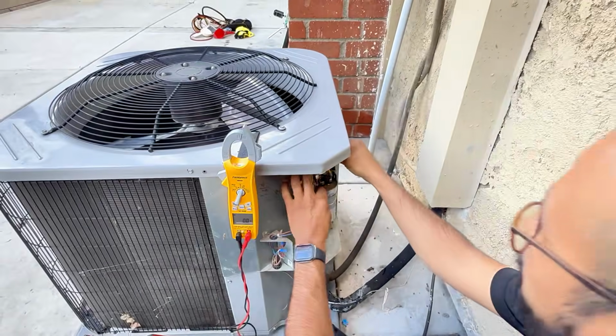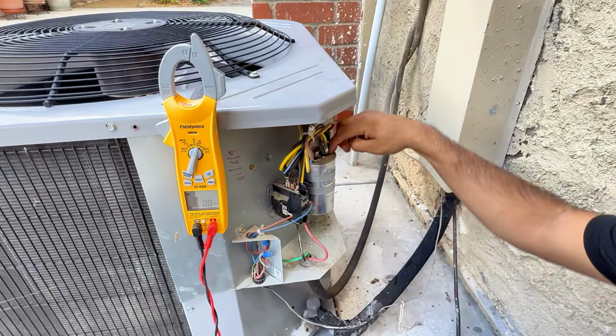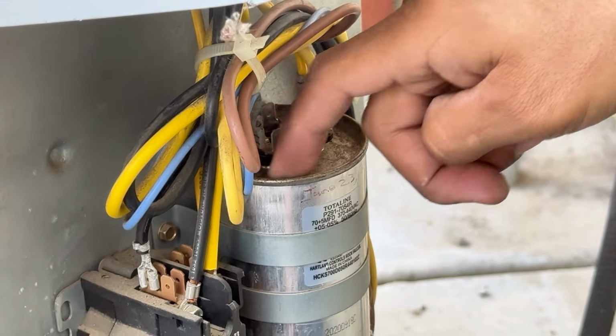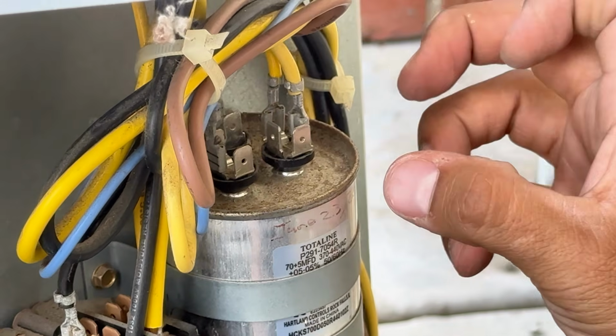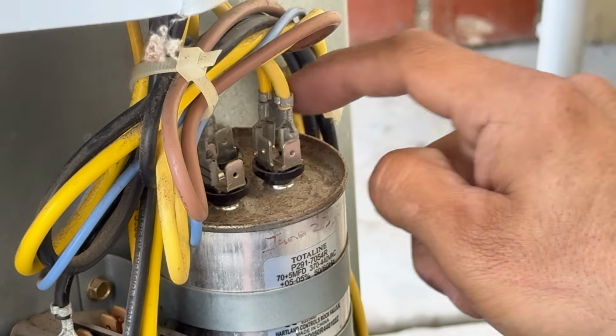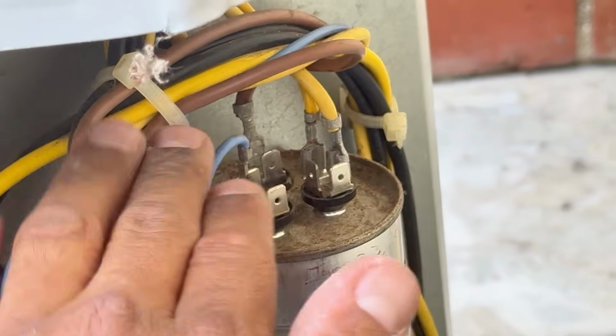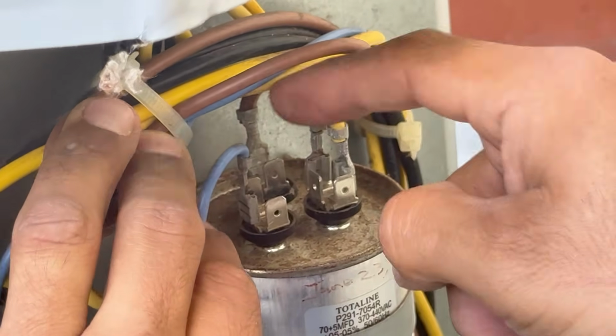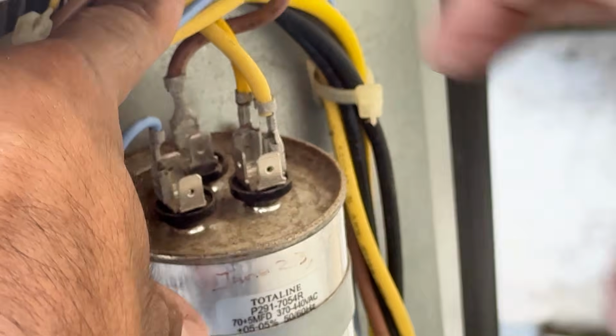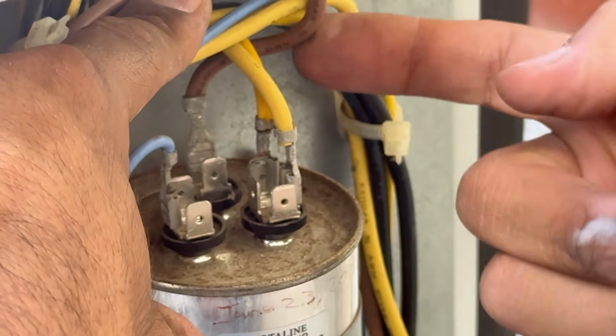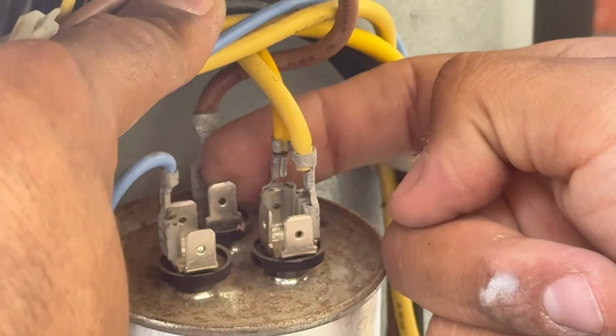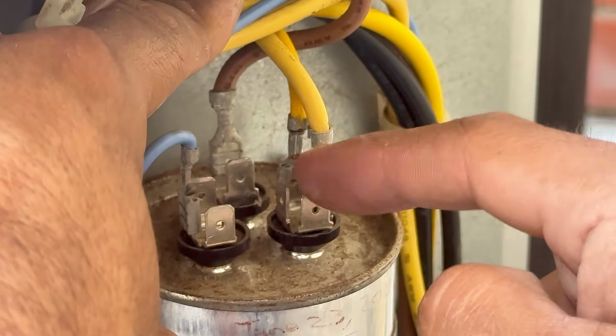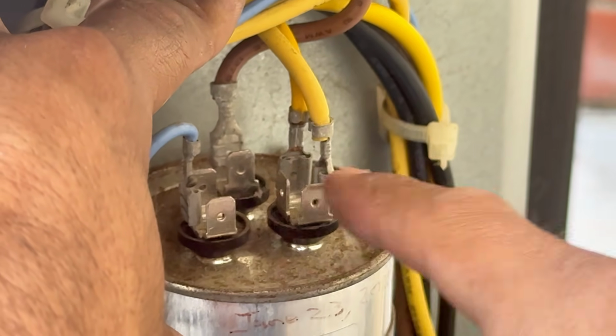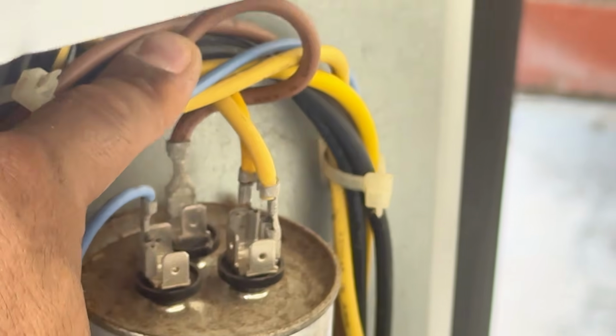A little tip here, guys. Your C, you see how all that's kind of rusty right here, right? So your C is the one with 4 terminals, 1, 2, 3, 4. Your Herm for your start winding is 1, 2, 3, it has 3. And then your condenser fan has either 2 or 1. You see the brown one, condenser fan, it only has two places to put wires on. The C has 4, 1, 2, 3, 4. And then the Herm, 3 right there.